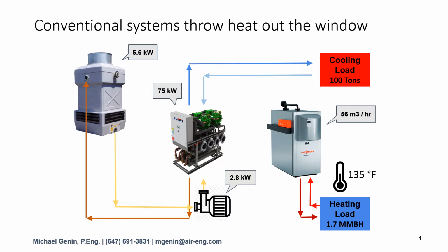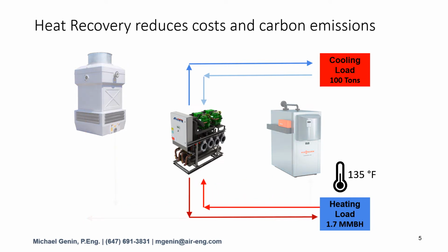Essentially, we are cooling the building and dumping the heat outside. Then we are using fossil fuels to regenerate this heat again for heating. Heat recovery. The process involves capturing this otherwise rejected heat and using it for the heating process. In this simplistic example, all of the heat from the chiller is recaptured, known as a simultaneous load.